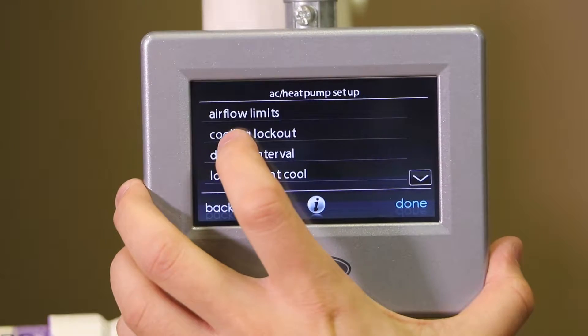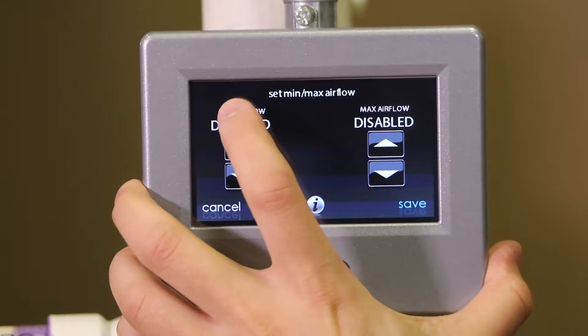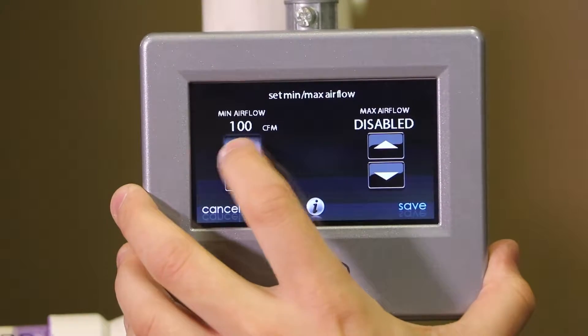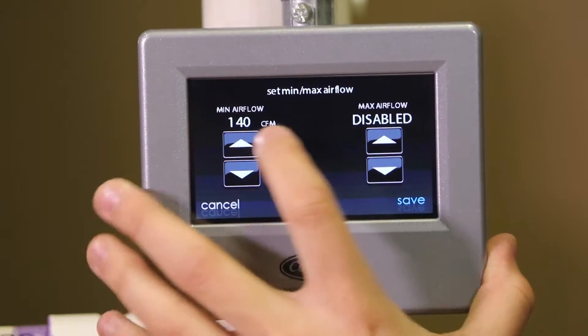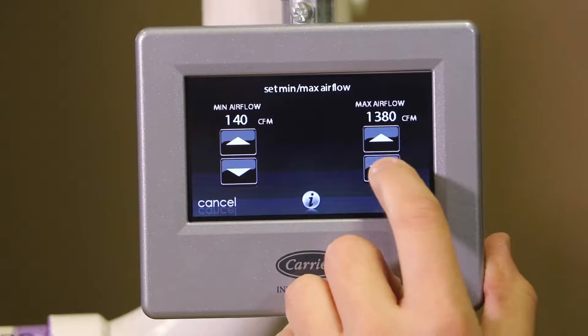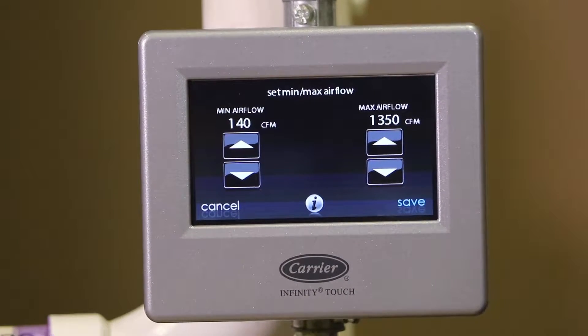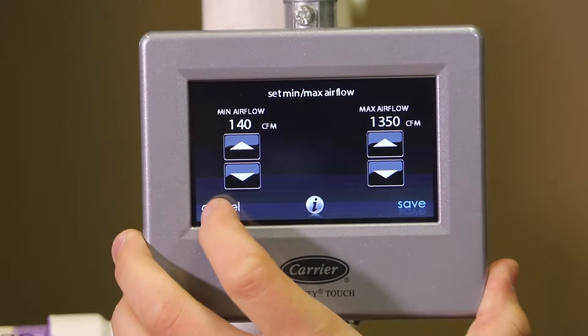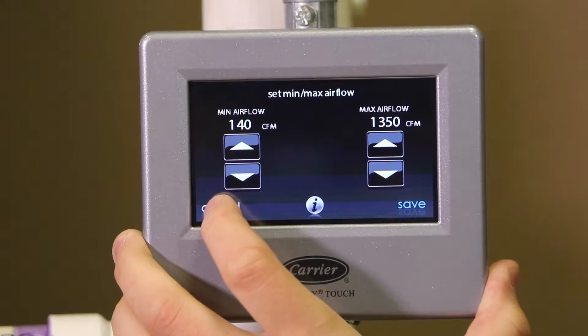Our first screen here is airflow settings — airflow limits. When I click on that, this is a very advanced unit that has a variable speed condenser fan and a variable speed compressor as well. I actually have the ability to increase the minimum air flows and decrease the maximum air flows on this particular system so it operates at a much tighter range. Normally you won't change this setting, but just know that it's here. You will not see this on the two and five stage Infinity and Evolution units.